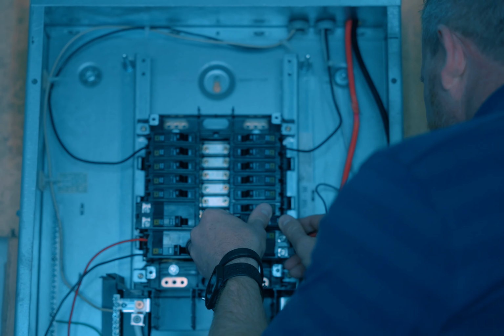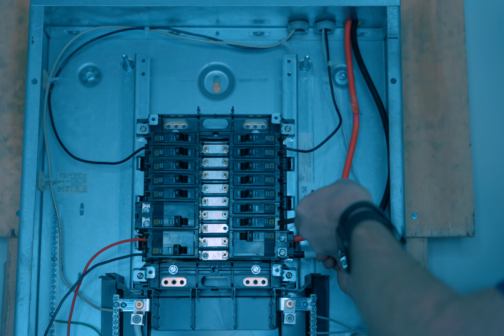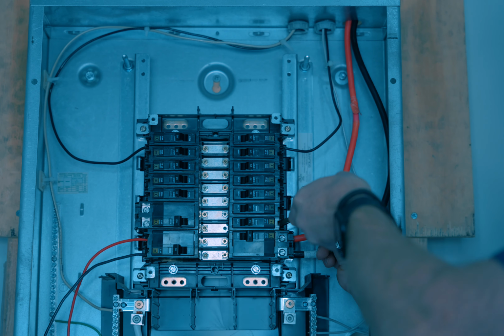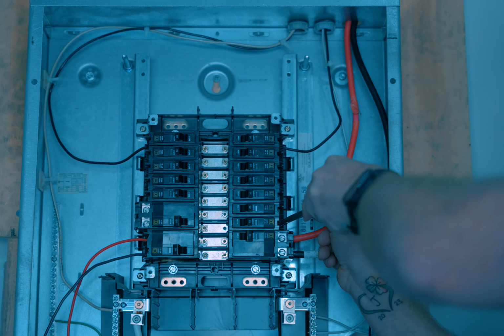Now that the circuit breaker is seated, we have to reinstall our load wire. Many new circuit breakers come with the screw already tightened, so loosen the load screw, then insert your load wire in between the two metal plates, not under the screw. When it's almost tight, hold the wire underneath the plate so it doesn't back off, and snug it down, not over tightening, but pretty tight. If you give it a pull check, it won't come right out.